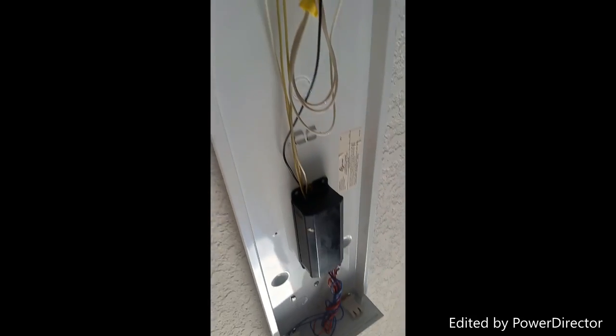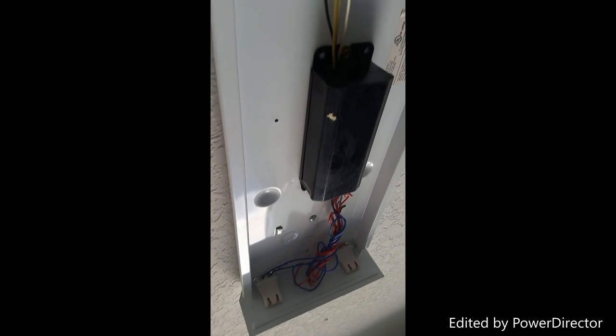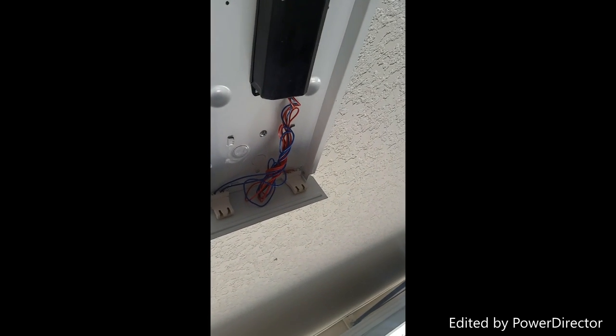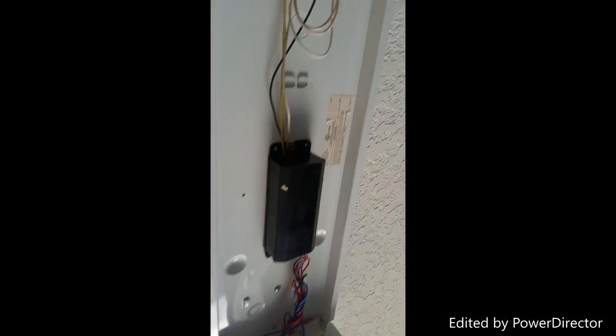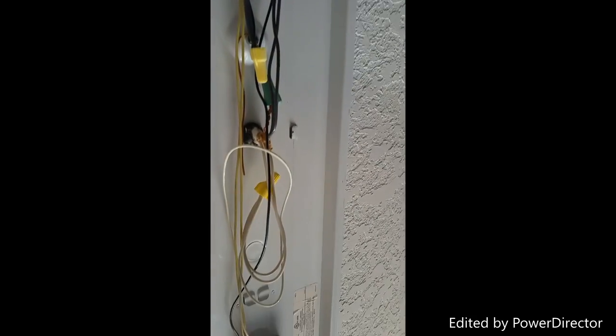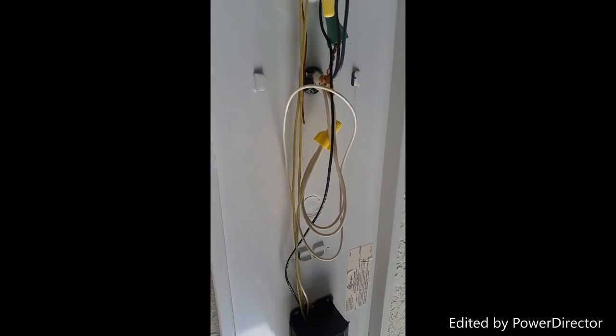And right there you have your ballast. Sometimes these ballasts will leak oil - obviously if that does, it's a bad one. Just this one was making a funny sound, the lights went out.